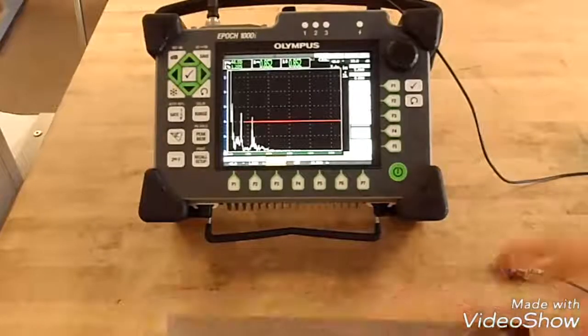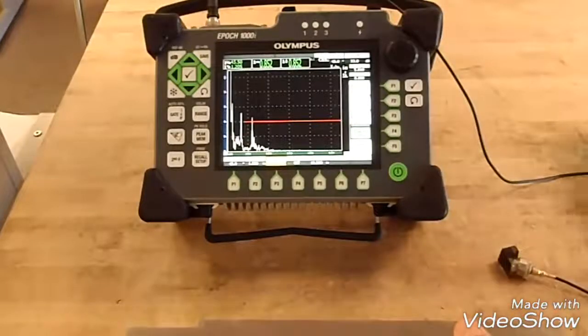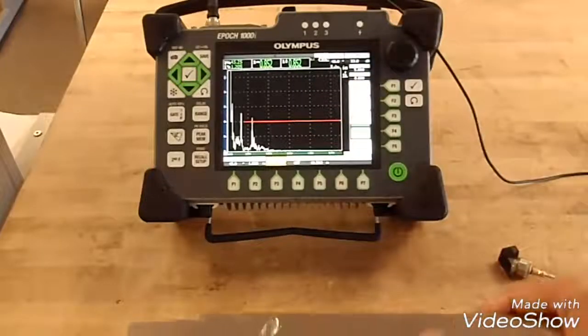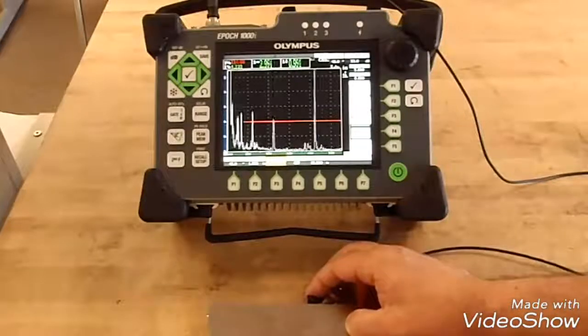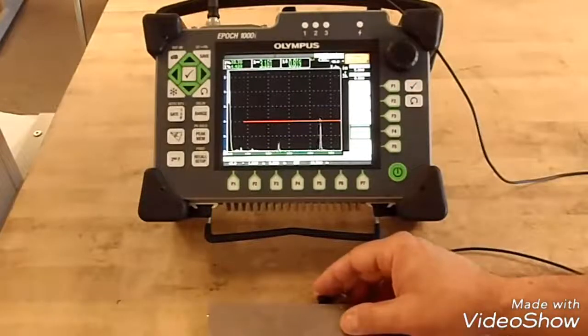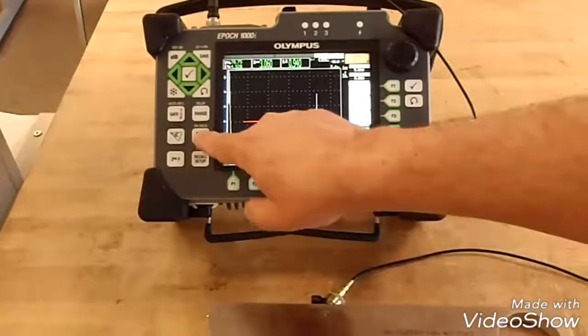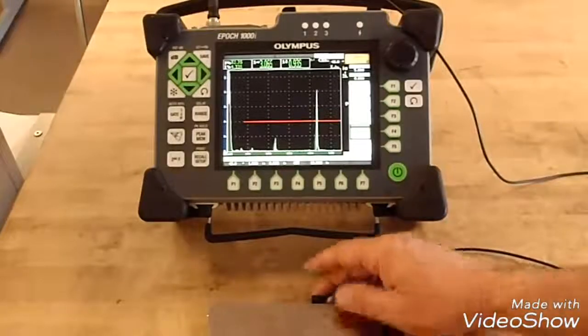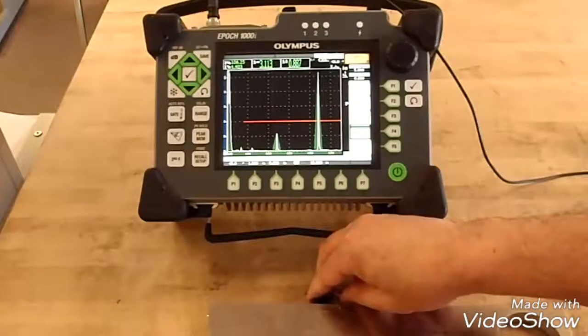Now the first thing you want to do is couple your transducer to your wedge and find your beam index point. Turn the gain down some so I can see that reflector. What's nice about this unit, you can use the peak memory and you can peak your signal.